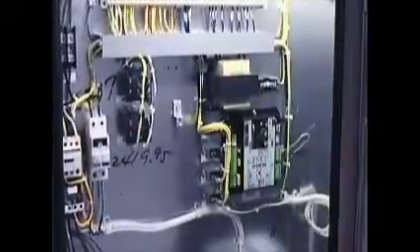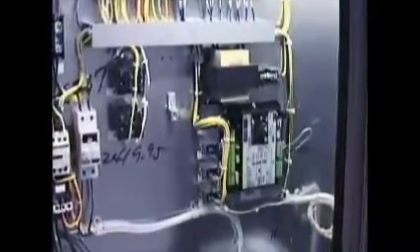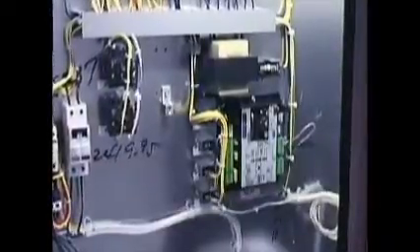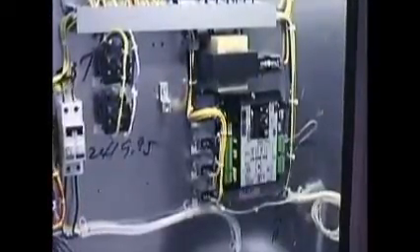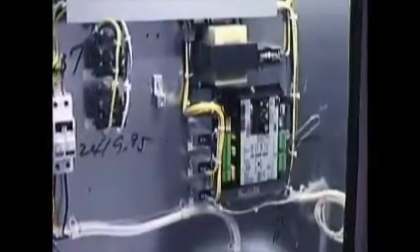Applied Air is going full bore with DDC controls. The IFL will come standard with a direct digital control system. Not only is the direct digital control system programmed to control the function of the unit itself, but it's also monitoring conditions, collecting trend information, collecting alarm conditions, and providing access to all that information either through a BACnet connection locally or even over the internet.